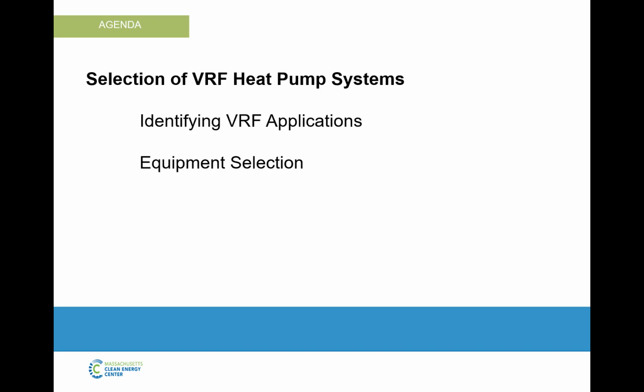Does that include fresh air integration? That typically does not. There are ways that it can, depending on how much fresh air is being brought in. That's not including the cost of a DOAS system or an ERV. If you're comparing to the PTAC style, just pulling some fresh air, 25 CFM into a fan coil unit, that would be factored in there. But if you're looking at a full built-up DOAS system, it's not.